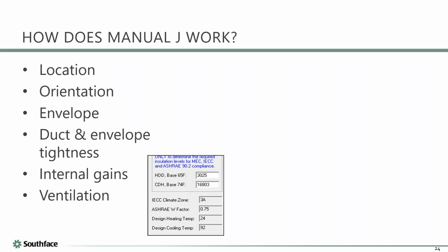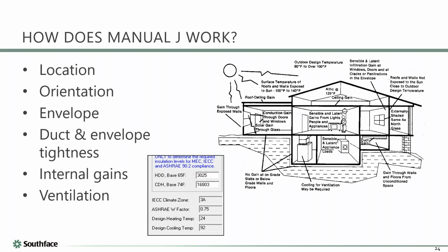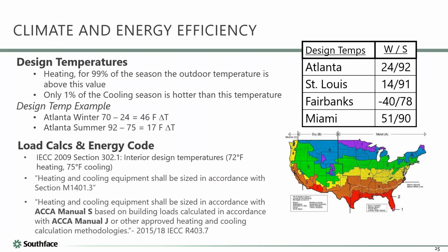Yes. What is it looking at when you do a load calc? It's basically looking at where this house is located. What's the climate like in that location? Which way is the house facing? What are the components that make up the thermal envelope? That would be how much insulation is there, how much surface area is there, what are the windows like, and so on. How leaky are the ducts? How leaky is the house? Where are the ducts located? What kind of internal gains are happening? Typical appliances like refrigerators and things that give off heat. And do you have any ventilation? If you have 50 CFM of outside air being brought in, what's the impact on the load? That kind of thing.